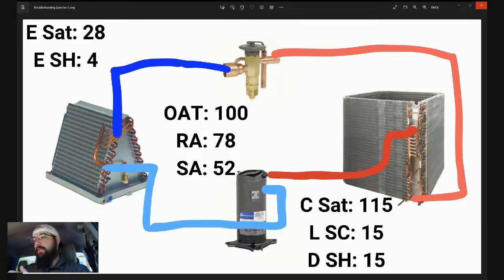I do see a high temp drop, low superheat. So superheat's 4, and the temp across, return air to supply air, is quite high. I see dirty coil coming in from James. Low saturation, low superheat, high temp drop, low airflow, fan speed too low. Okay, so let's dive into it. All right, so we think it's low airflow.